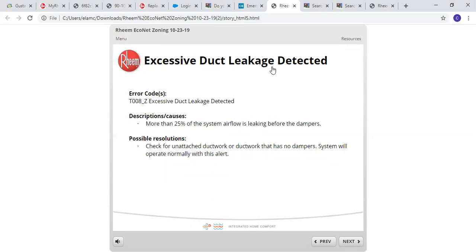Now here's a good one: excess duct leakage detected. T008Z, excessive duct leakage. I mentioned this before, so if you've got, well, let's just say you got everything ducted, but you've got a mud room or something off to the side that you don't really care about zoning that. It's not a big deal, so you just don't zone it. You just leave those free flowing.